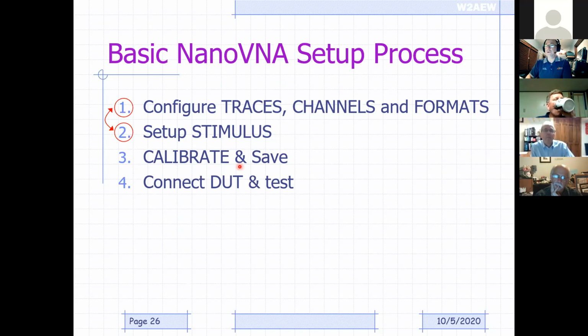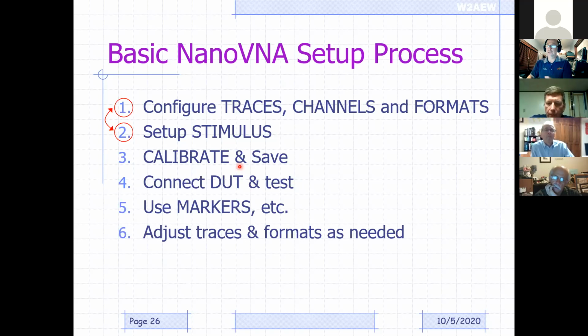And then you connect up your device and you make your measurements. You can throw on markers, adjust any traces and formats. You can add traces, take things away. As long as you don't change the frequency range, you can just add and subtract traces and things like that, and do that as much as you want. Because all those measurements are literally all just different math on the same set of computed transmission and reflection properties of the device.